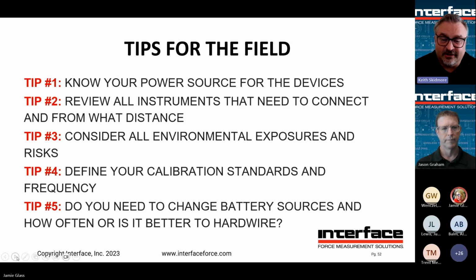Again, calibration, standards, and frequency. Sometimes in the field, it doesn't make sense to pull sensors and send them back for recalibration. A lot of times, field calibration is not only possible, but maybe the most desirable method, especially for something like a pin that's in a crane. It's really best calibrated in that situation versus sending the pin to the lab. You really want to calibrate the whole assembly, including the sheave and the interface mechanically to the pin. So picking up a known weight, or having a company come out with known weights and doing an on-site calibration may make the most sense.